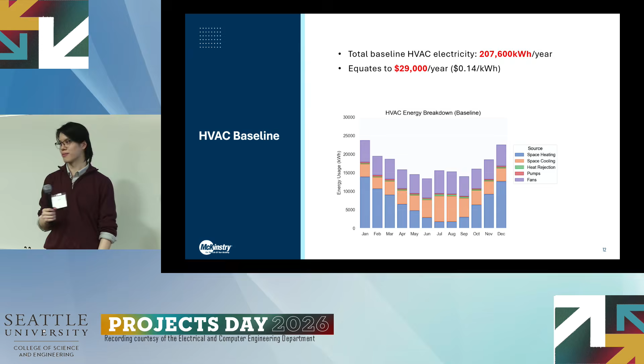So we're going to start with our HVAC optimizations. This is our baseline model provided by McKinstry, showing the energy use specifically for HVAC systems over the year, month by month. We used this model to test each control optimization strategy individually and then compiled them at the end. Our baseline HVAC electricity use was over 207,000 kilowatt hours per year, which equates to around $29,000 with a 14-cent kilowatt hour conversion.